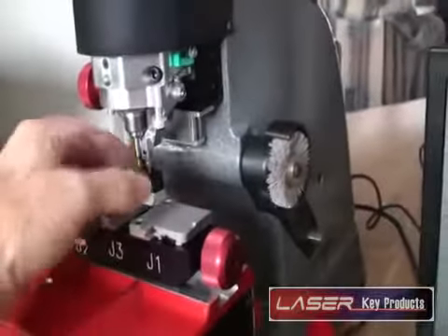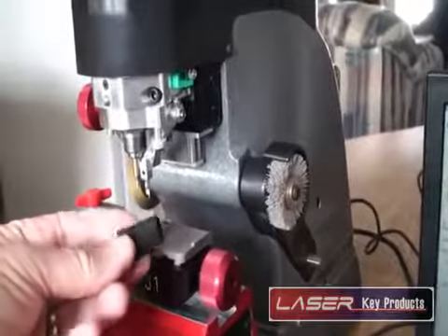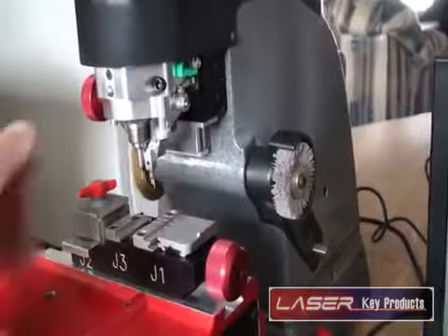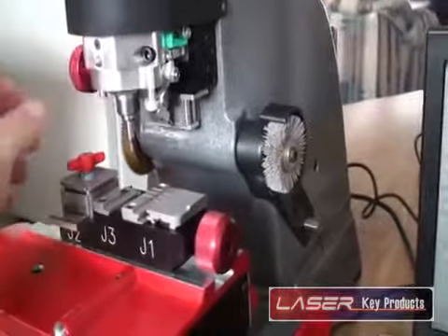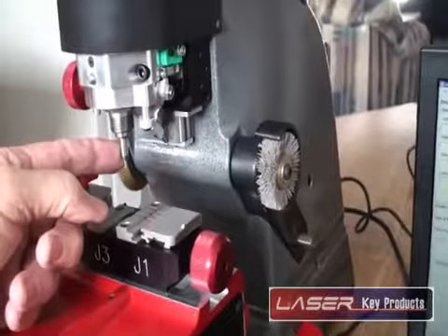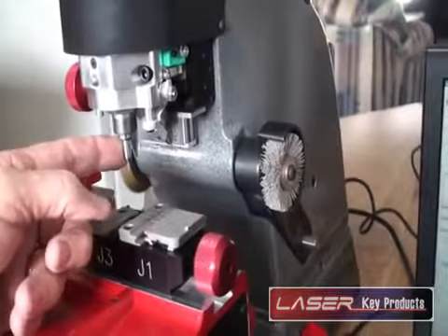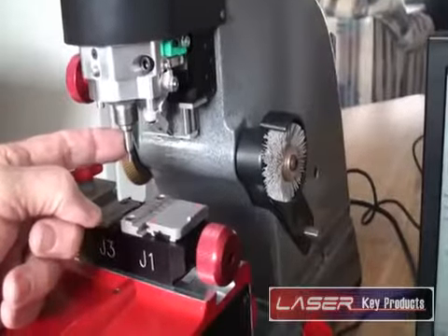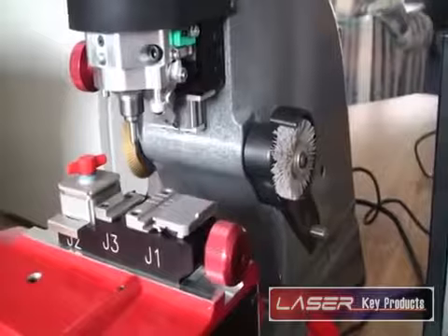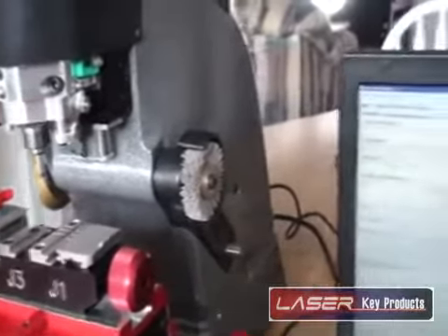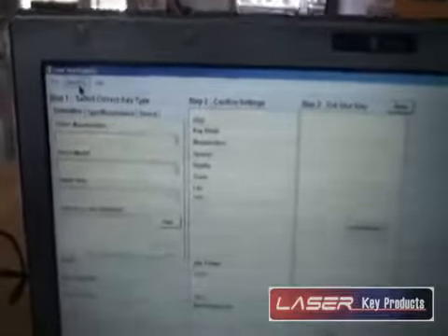So first thing you want to do is take off your little sponge device and save that for later shipping if it has to come back. Raise your tracer. At this point we send the machine out with a calibration tool in place instead of the cutter. The cutter comes separately. So what you want to do now is go into the calibration process. You go to the software, click on operations, calibrate cutter, and since I want to do jaw 1, I put in the number 1 and hit OK.